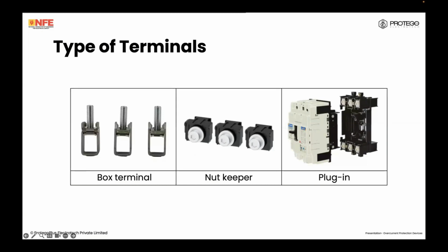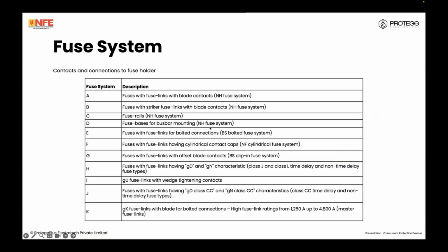system. This is just for your reference, because oftentimes when you're specifying a project, you see 2 part numbers for the same tripping characteristic, same circuit breaker. Those part numbers actually correspond to the fact that one MCCB or one fuse or one circuit breaker has box terminals and one has nut keeper terminals. Depending on the wiring system, depending on your infrastructure on site, you will then choose between these. Fuse systems, there are various fuse systems. We won't get into this in greater detail. Depending again on your structure and the system, you can choose a system.